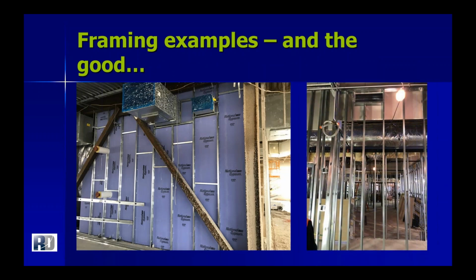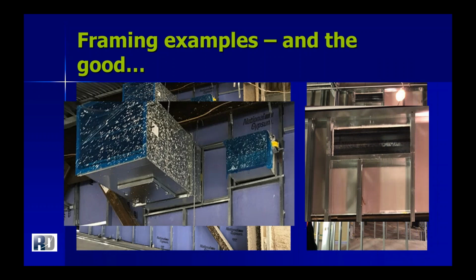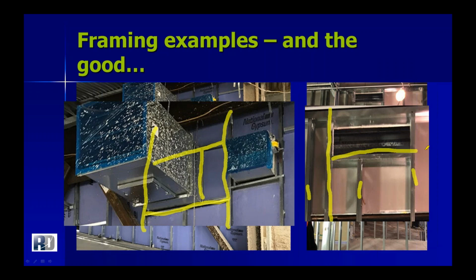Here are some good examples. As you can see, these dampers show framing underneath. It's important to see that these dampers have a vertical stud that extends from the floor to the deck. Then the horizontal studs connect to those full-length vertical studs. I'm going to attempt the highlighter again. I apologize if I get us messed up. We've got these horizontal studs here that are connecting to these vertical ones that go all the way up and all the way down. And then because it doesn't fully fill in the space, they connect this intermittent one to those two that went to the full vertical. Over on this side, you can see they had proper spacing for their studs, and they chose to add another full stud to connect their horizontals to.